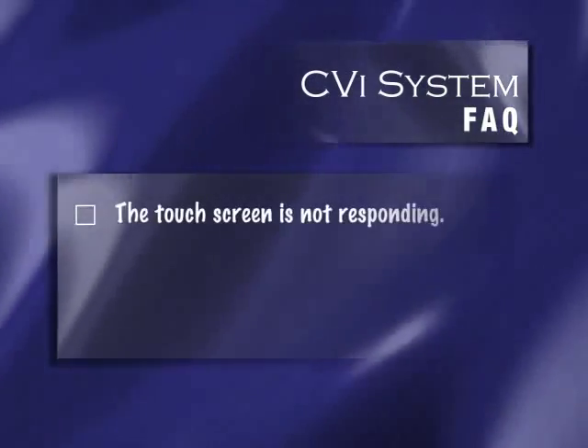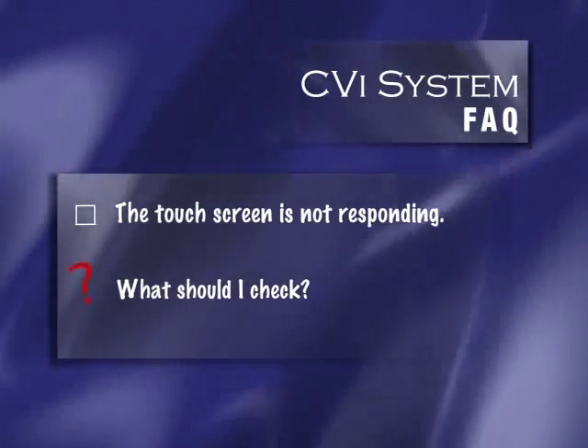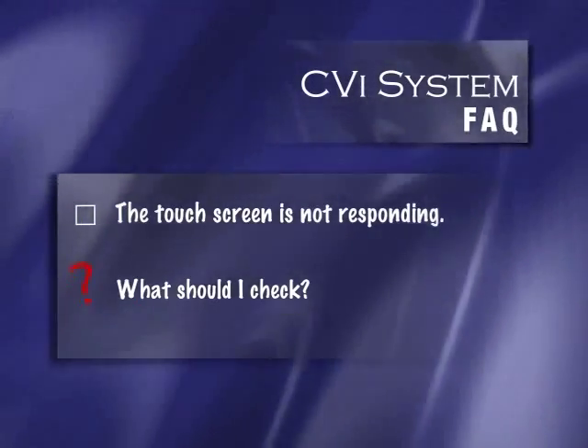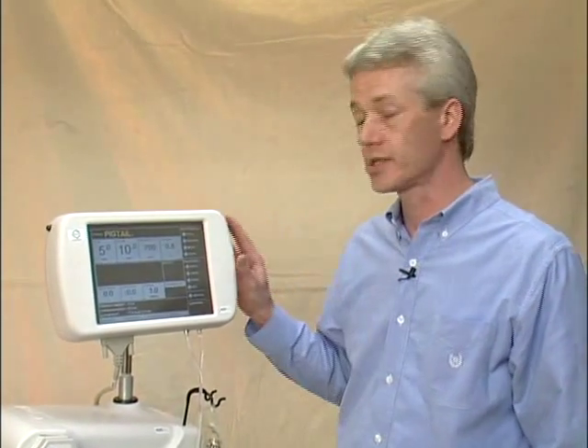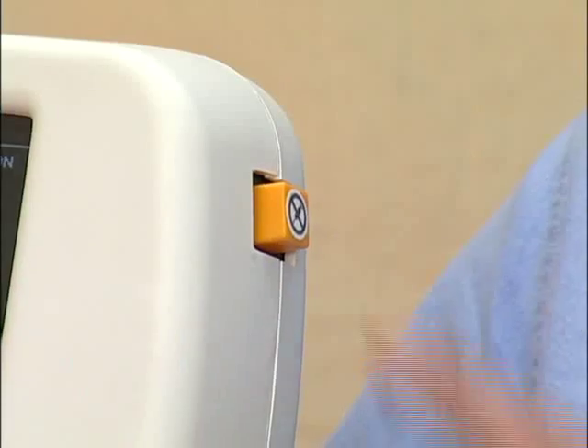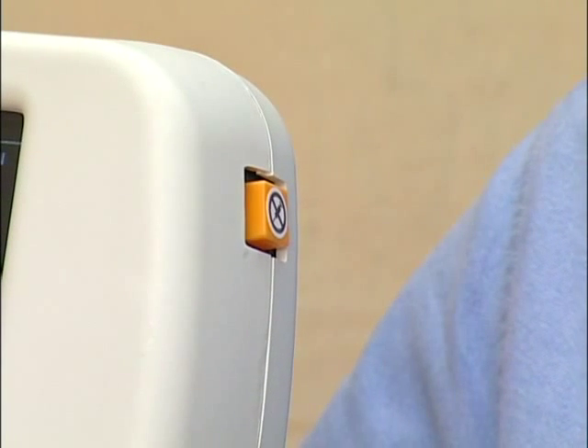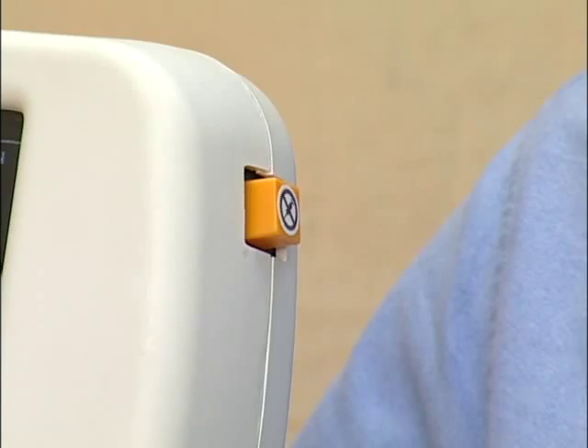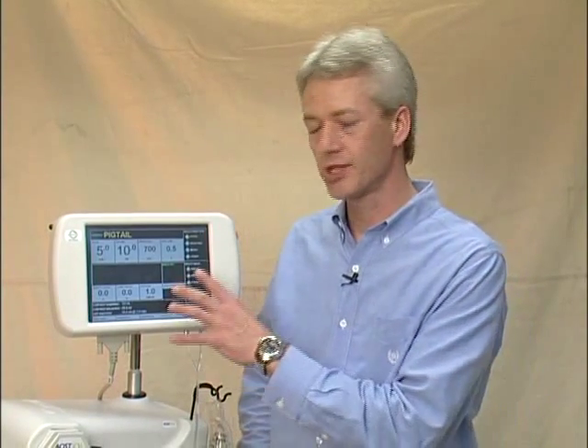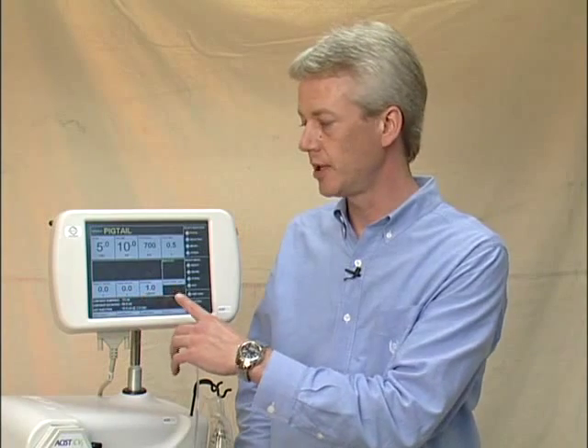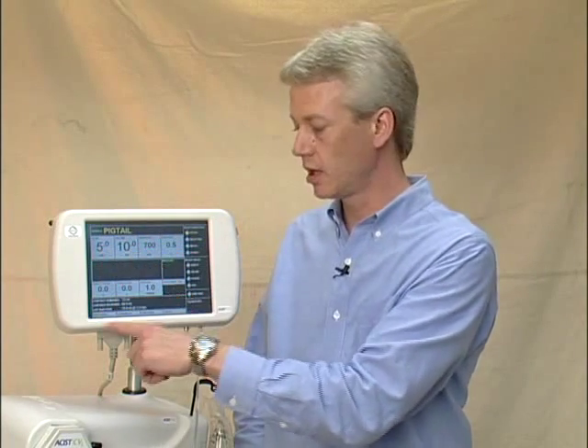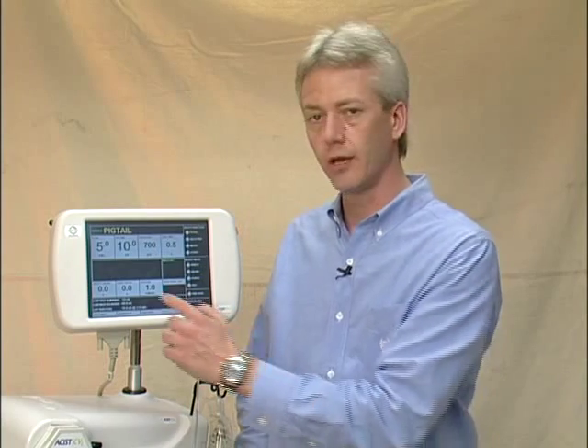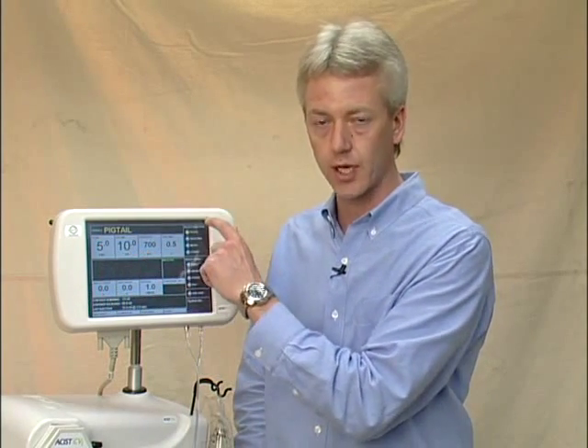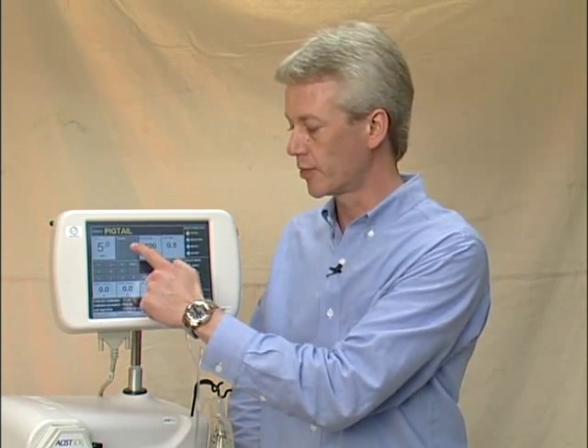There seems to be something wrong with the touch screen. Either the command does not work or the touch screen is not responding correctly. If the touchscreen is not responding correctly, the very first thing to check is to verify that the standby switch is not engaged. When the standby is engaged, this disables the screen, and so nothing on the screen can be activated. The other factor that can affect the screen responsiveness is the calibration. This needs to be done with a completely clean screen with no contrast on it and being very accurate as we touch the 3 crosshairs during the calibration mode of the system. If this is done, the screen should respond appropriately for every touch.